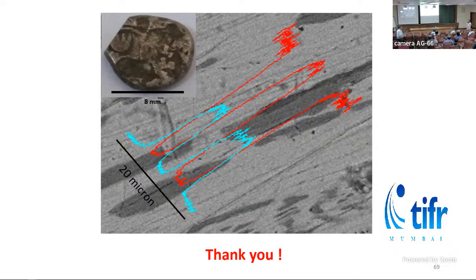How do you calibrate? In case of an aberration corrected microscope, it depends on at what magnification you want to image the sample. If you really want to go to that atomic level, then yes, before loading the sample, you need to do that alignment. Other microscopes, we can do it, let's say, once in 3 months or so. For a probe corrected microscope, it is just before loading the sample, if you want to image at atomic scale.